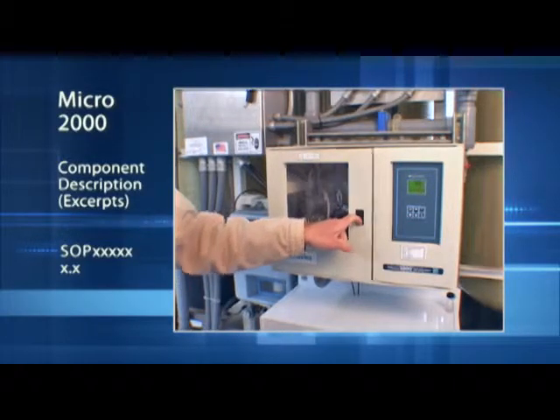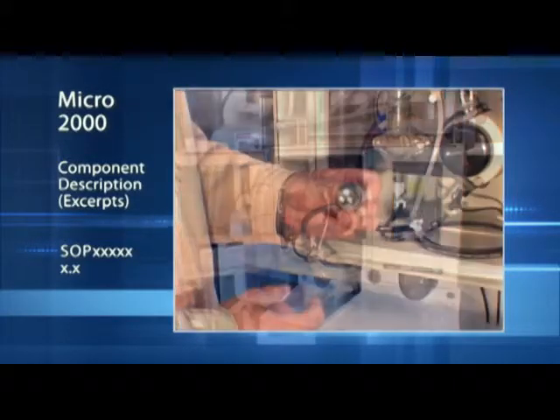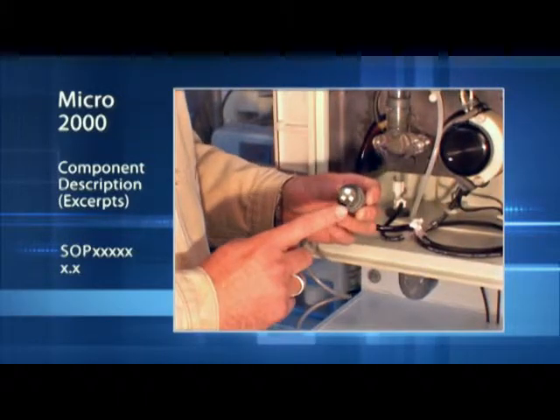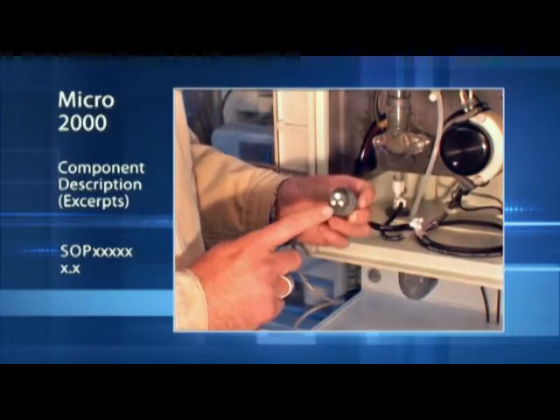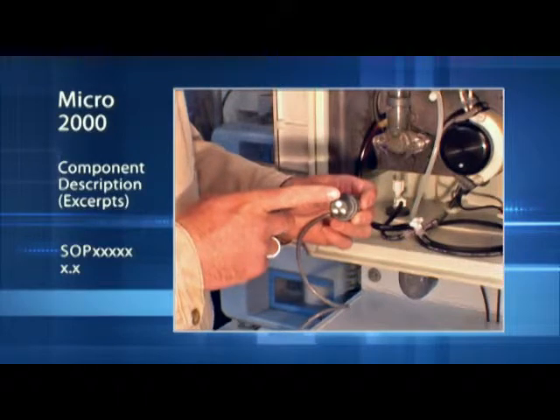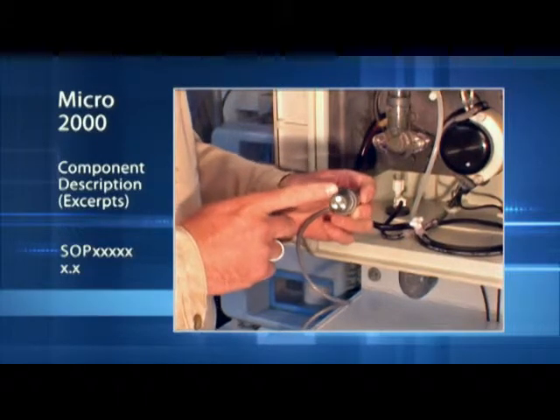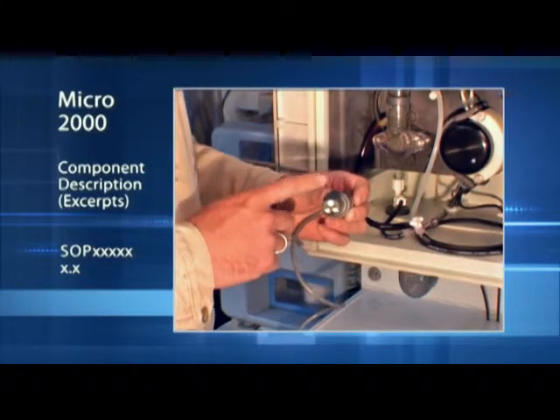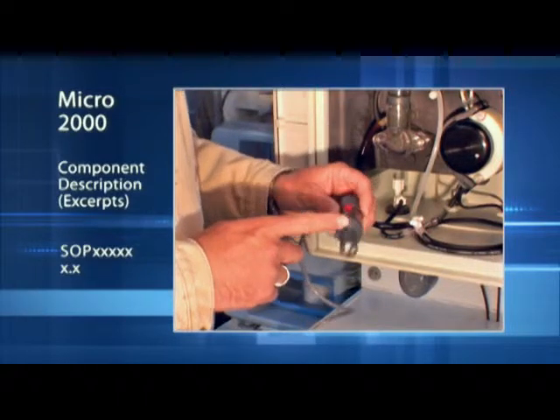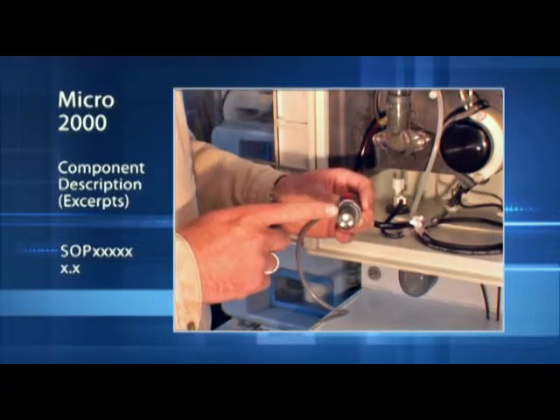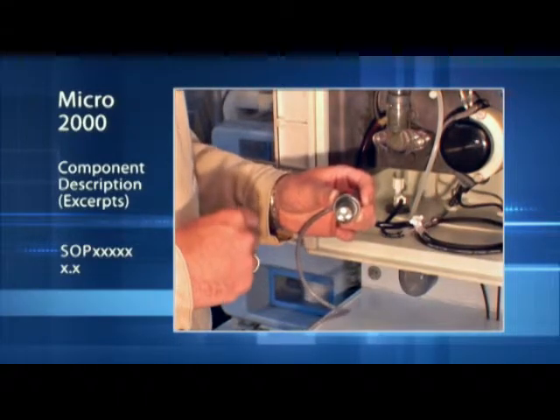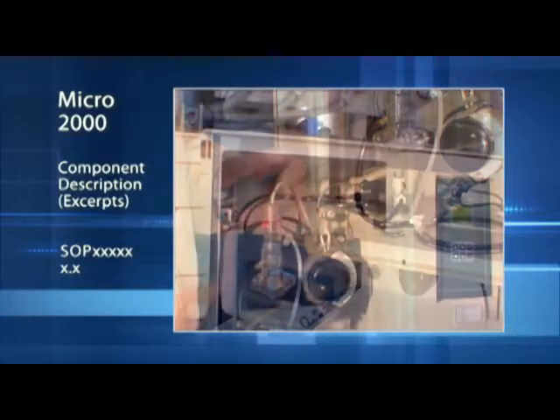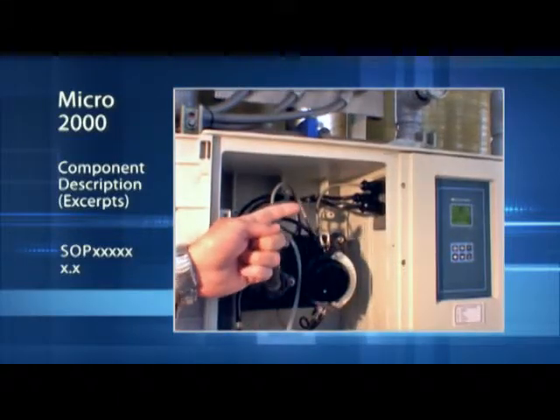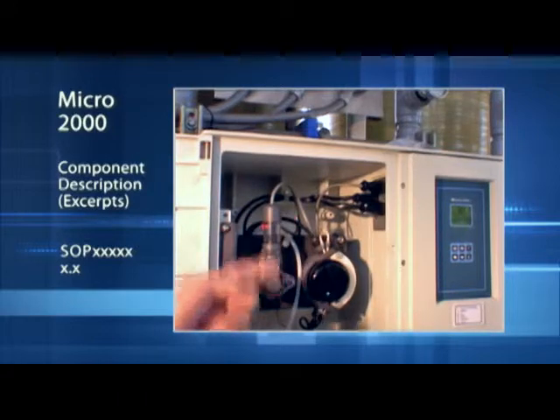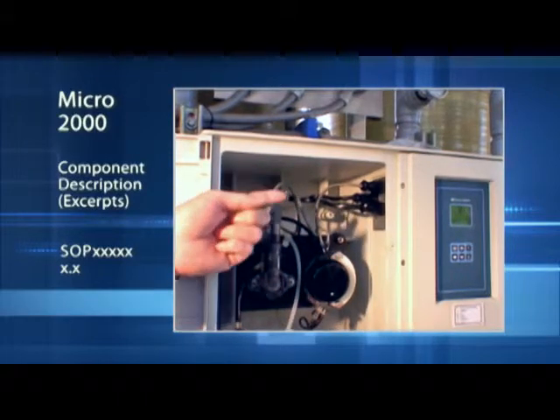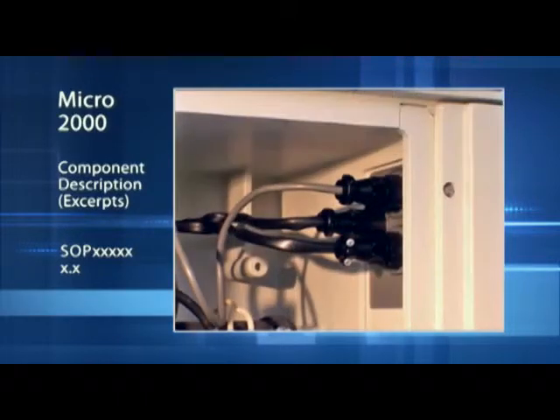If we were to open it, we'll look at the inside. The probe consists of 2 titanium electrodes here and 1 white porous element. This porous element provides a flow path with electrolyte stored on top to flow into the sample chamber while the unit is running and analyzing the chlorine. In the top right corner of the box, you have 3 connectors, one for the pump, one for the probe, and one for the cell.